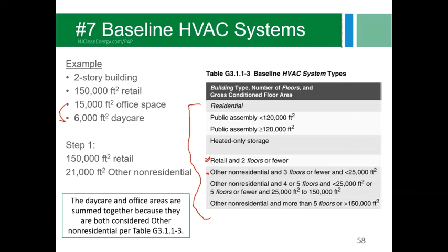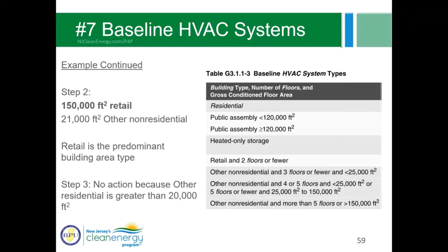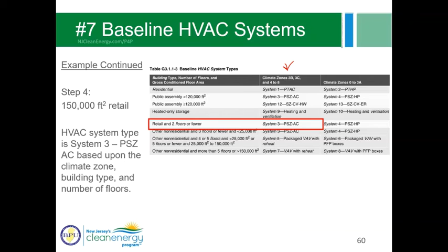Step 3, this is where if you did have building types less than 20,000 square feet, you would basically get rid of them, forget about them, and take their square footage and add them to the predominant building type. So if I had a 10,000 square foot public assembly area, then I would just add that to retail and it would become 160,000 square feet. Step 4, determine the HVAC system type for predominant building type. So in the case, I have retail, and it's two floors or fewer. As we said, it's a 2-story building, and our climate zone is 4A. So we can pretty easily see that it's system 3, package single zone AC.